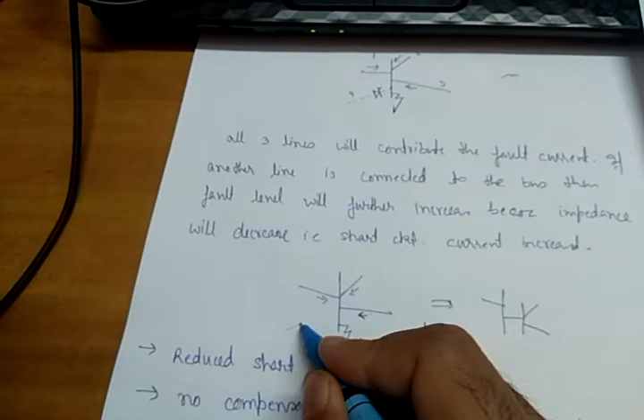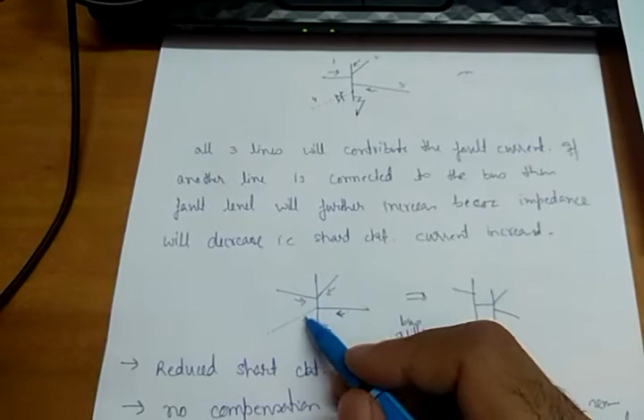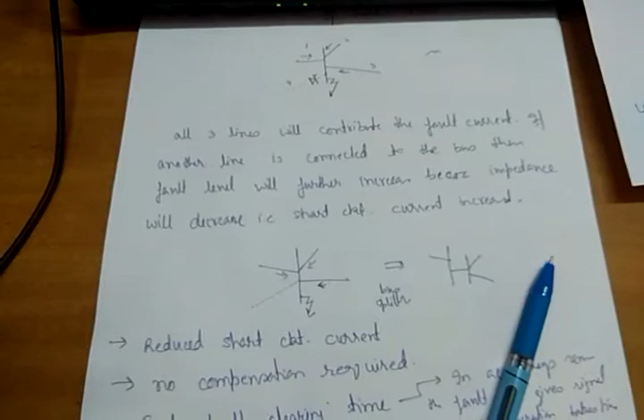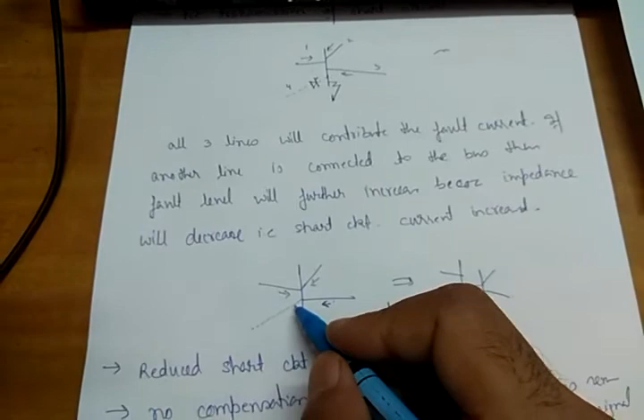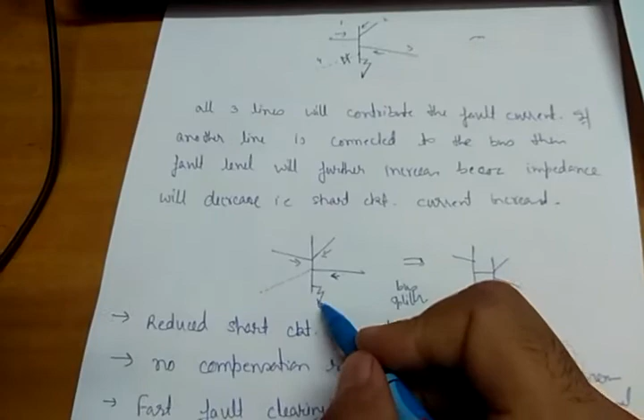Suppose this is a fourth line which I am installing. Since all the lines are connected in parallel to this bus, what will happen to the impedance to the fault? If the lines are connected in parallel, the line reactance decreases. If one line has a reactance of 2 ohm and I use two lines in parallel, the overall reactance will be 1 ohm. If the reactance decreases, the impedance to the fault decreases, so the fault current will increase further. There will be more short circuit current in AC.